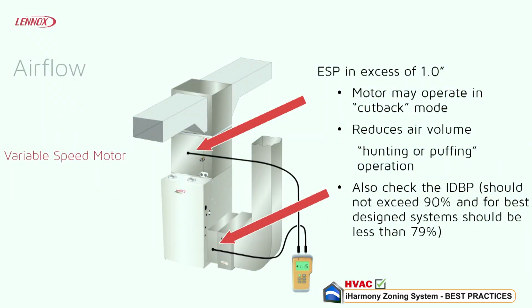So when you go into the settings, as you go through all the settings when you first start it up, there's a spot, and most people skip it. It tells you each zone how many CFM that's adjusted, and with more classes and with information from the comfort advisor, we should better know each zone, how many CFMs to adjust that to. We went back a couple times, and I think I spoke with you over the phone, Mr. Brandon, and we were able to figure it out that we have to adjust each zone to a certain CFM. And that was causing the unit would vibrate when you had a smaller zone running triple the CFM it should be running. There was times the unit would even vibrate. Homeowner system didn't shut down. It was just the noise that it was creating for having one zone open with more CFM than what it can handle. That's very important.